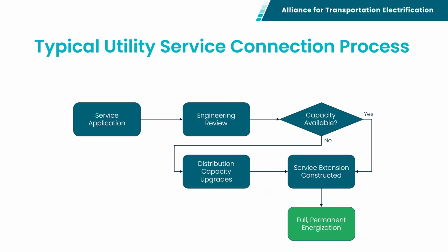So when we hear about transformer shortages, permitting timelines, or the energization queue at the utility, a lot of that has to do with constructing that service extension. If distribution capacity is not available, then in addition to the service extension, we also have to do distribution capacity upgrades, and that's when we start to trigger years and years of potential delays. That's the piece we're talking about when discussing constraints in the distribution system and easing timelines there. We're not covering permitting or transformer shortages in this particular paper, though we've addressed those in prior papers.